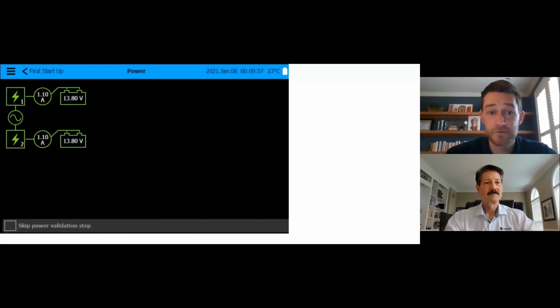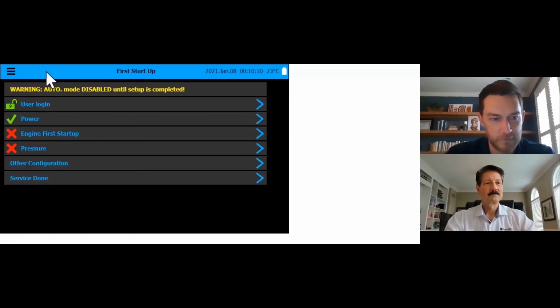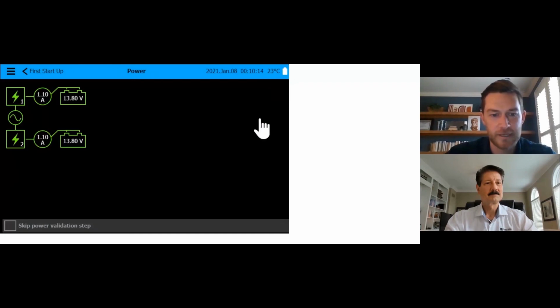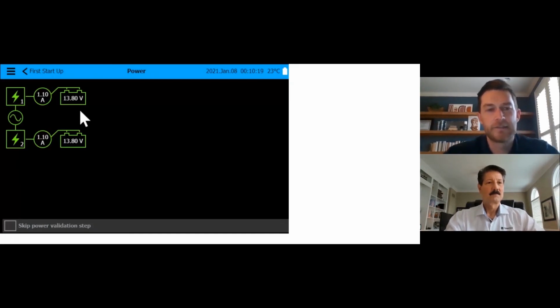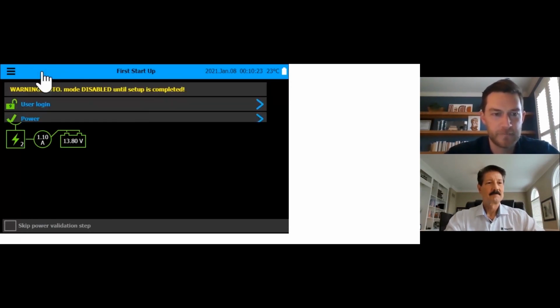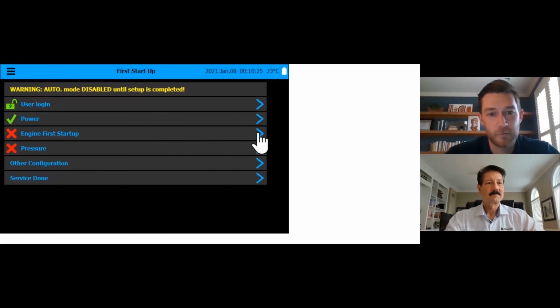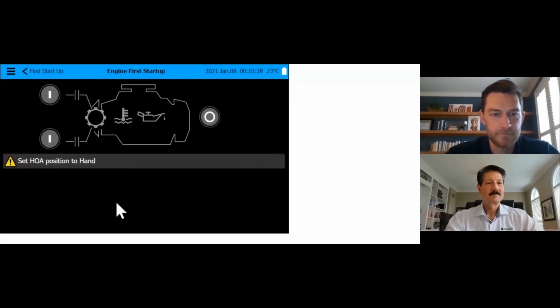So the first thing is to check the power, which with the diesel is just 120 volt coming in. That's basically just to feed the chargers, which then feed the battery. So you can see right there that we've got amperage going to the batteries, and the batteries are already at their 13.8 volts. So everything is good and healthy there. You can see that it's already got the check mark saying that it's good to continue on the startup. If the batteries were not charged yet, you would have a red X on that one.